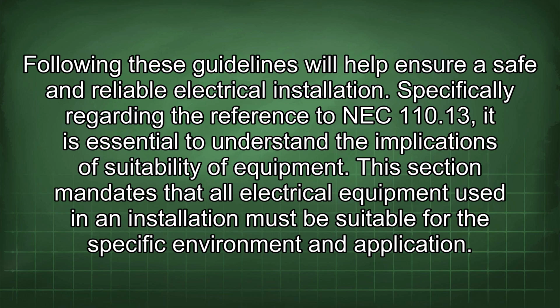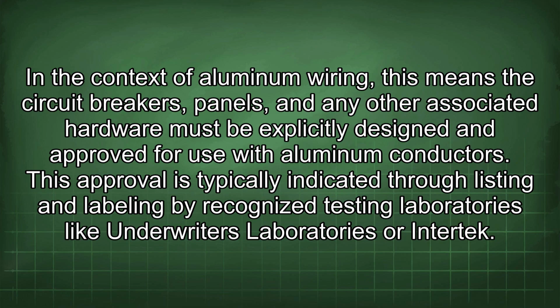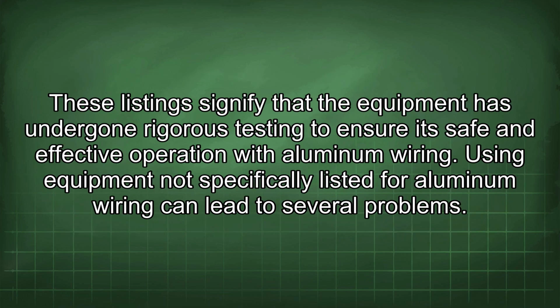Specifically regarding the reference to NEC 110.13, it is essential to understand the implications of suitability of equipment. This section mandates that all electrical equipment used in an installation must be suitable for the specific environment and application. In the context of aluminum wiring, this means the circuit breakers, panels, and any other associated hardware must be explicitly designed and approved for use with aluminum conductors. This approval is typically indicated through listing and labeling by recognized testing laboratories like Underwriters Laboratories or Intertek. These listings signify that the equipment has undergone rigorous testing to ensure its safe and effective operation with aluminum wiring.